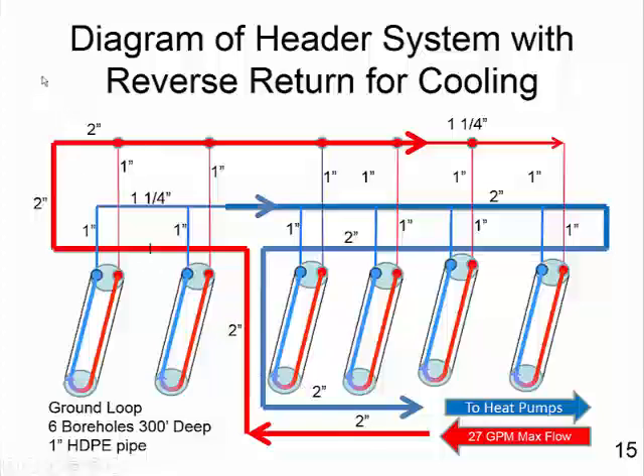This is what the diagram looks like of the header system with reverse return for cooling. Here we see a 27 gallons per minute maximum flow going into the system. The red indicates the water is warmer. It goes around in a 2-inch pipe, and then as it starts into the other pipes, here's a 1-inch pipe coming down, another 1-inch pipe coming down, filling up the boreholes.